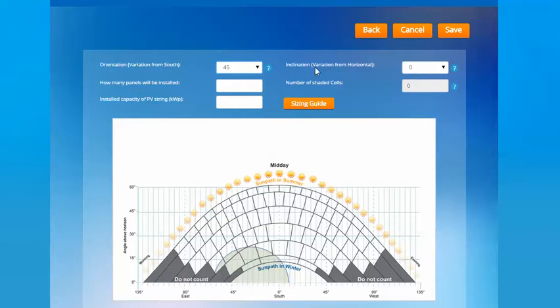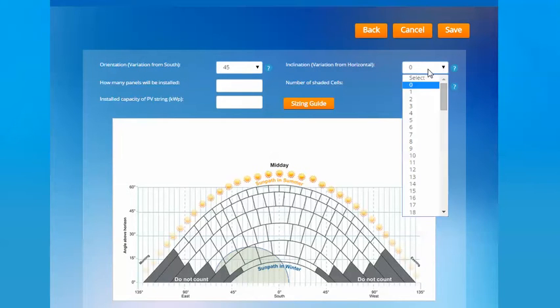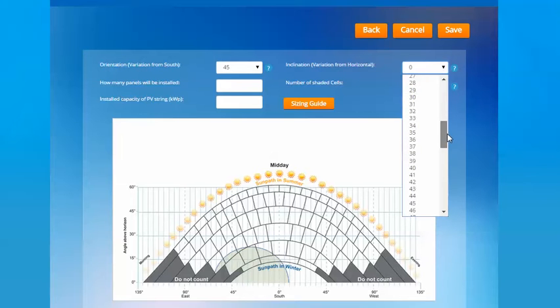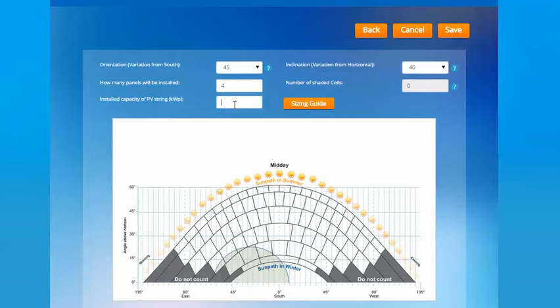Also the inclination, so it's the variation from horizon. This is essentially the angle of the roof. The optimal angle for solar power collection in the UK is 35 degrees however most roofs in the UK have a typical angle of 40 degrees. You should collect an exact estimation of this though based on the property you're installing on. Then you need to add the number of panels and the total install capacity of the PV string. So this is the capacity of the string as a whole rather than the individual panels and should be entered in kilowatts.